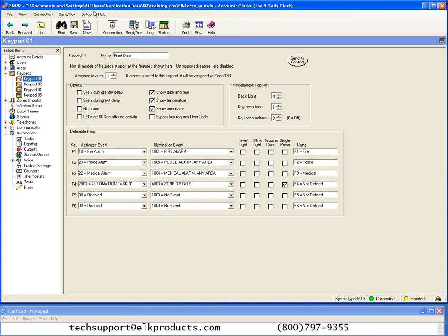You can write rules. You can set up an analog zone. That's one of the zone definitions. And then you can write a rule to trigger on different voltage readings on that zone. But it's like 7.2 volts. It doesn't really drill down into small amounts of voltage. So the millivolt part of that is where I'm thinking no. But the system does support analog zones that can be triggered off of different voltage levels, between like 0 and 13.8 volts.